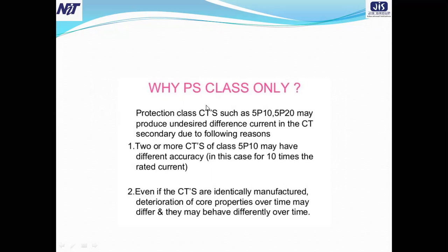Now, why PS class only? You know the word PS class. Let me talk about the PS class. Why this PS protection class? Current transformers such as 5P10, 5P20 may produce undesired difference current in the CT secondary due to the following reasons. Two or more CTs of class 5P10 may have different accuracy, in this case for 10 times the rated current.